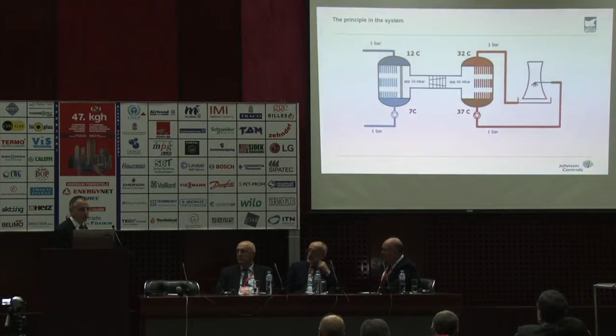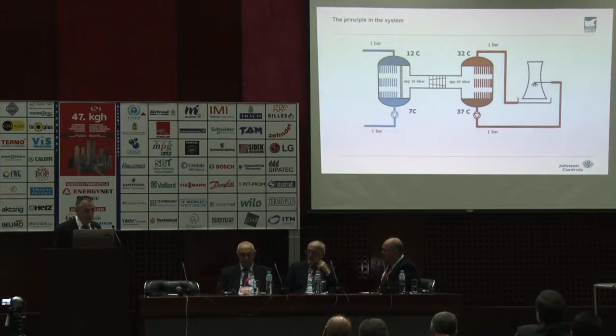The condenser water will come back here in this case as the water will be fully saturated with air. So the trick and the patents around the whole technology here is about how to separate the air from the water, because if there gets too much air in, you cannot keep down the condensing pressure and you will lose all your efficiency. So that's the trick. Otherwise, you will spend a lot of money on vacuum pumps.